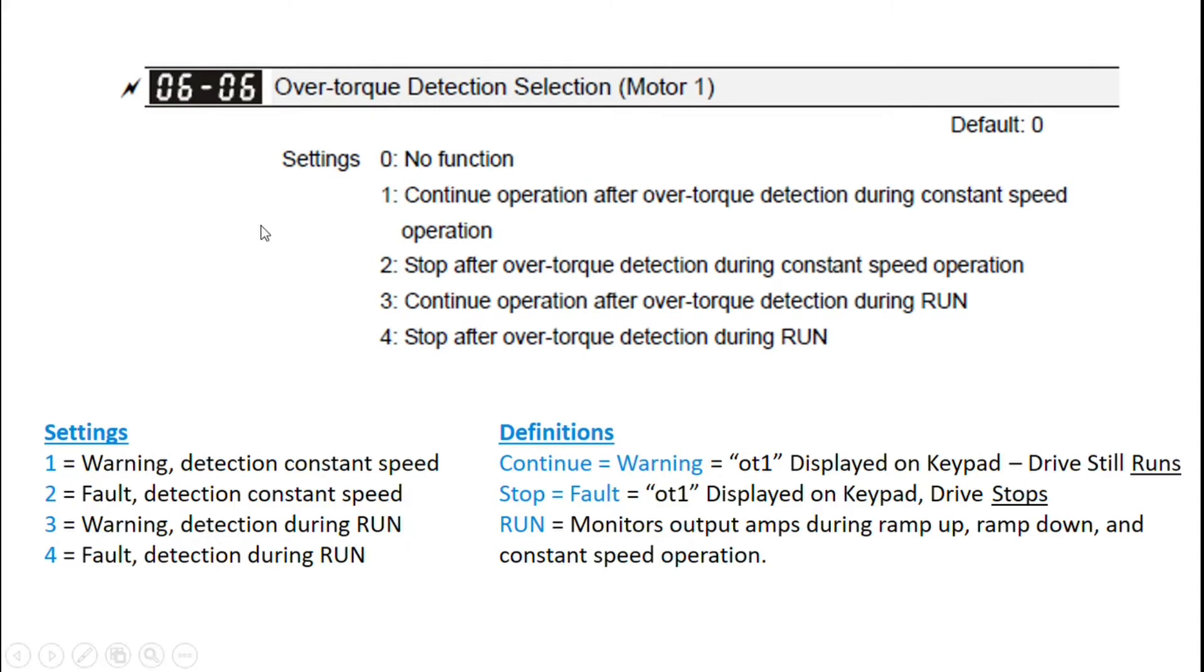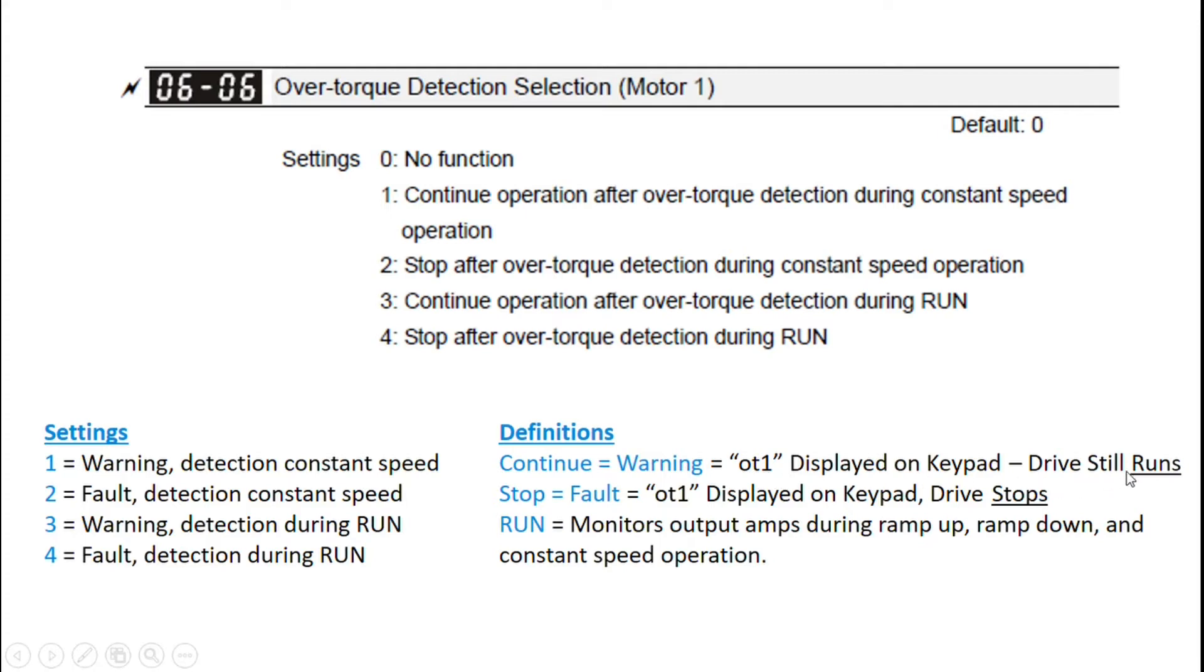So options one and three both say continue operation. That means if over torque is detected, it's going to show a warning. So it's going to show the OT1 on the keypad, but the drive is going to keep running.